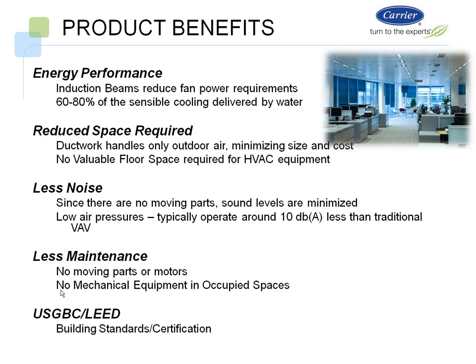And again, for USGBC and LEED, we've done some modeling with the Carrier hourly analysis program, and we modeled this versus an ASHRAE 90.1 type project, using our series counterflow chillers in a typical 25-story building in Charlotte, North Carolina, using air handlers and these induction beams. It is 15 LEED points. And that was being very conservative on our side, as well as reducing the energy cost by about 40% in comparison. So a lot to do there.